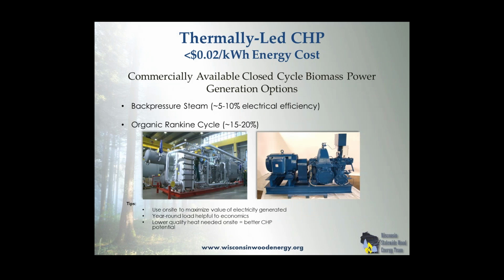Thermally led CHP, when we say less than 2 cents a kilowatt hour, these systems are generally 95% overall thermally efficient. Basically what happens is you're taking higher pressure steam, you're dropping enthalpy from that steam, and it's turning that into work driving the turbine, and really what you lose, or the inefficiency, is generally in condensate. You can do superheated steam, but typically in our boilers and systems we start out with saturated steam.